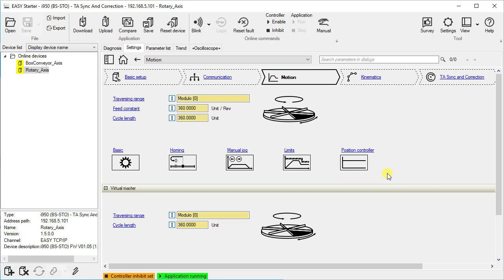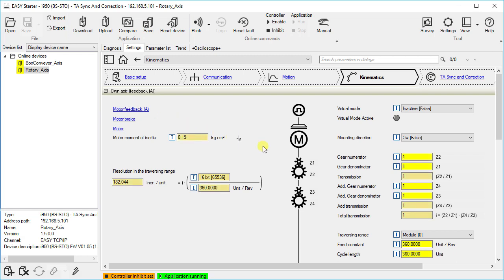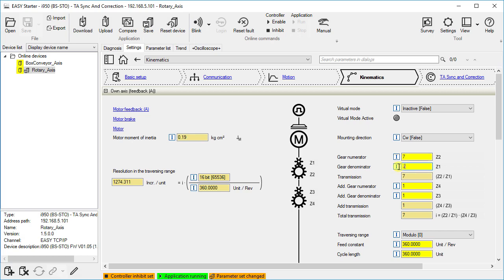First we will set the kinematics. We can click on the commissioning step or follow the linked text of traversing range or feed constant to open the interface for the kinematic parameters. Here you can set the mounting directions, gear and/or transmission ratio of the mechanics. By entering the numerator and denominator of the ratio, the exact factors can be set, which are very important especially for endless traversing ranges. Please do not use rounded values for the ratio here, but rather determine the exact setting values from the gearbox catalog or data sheet.